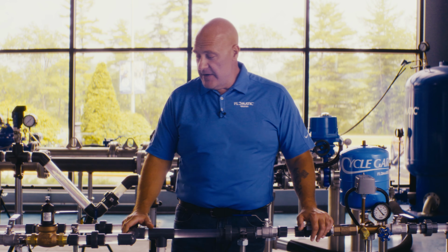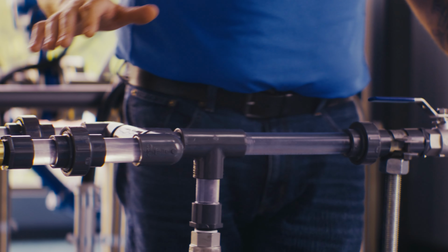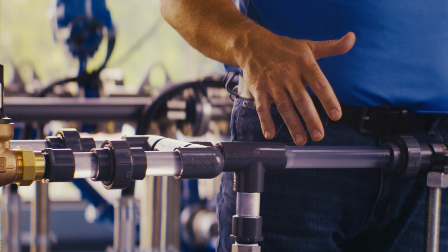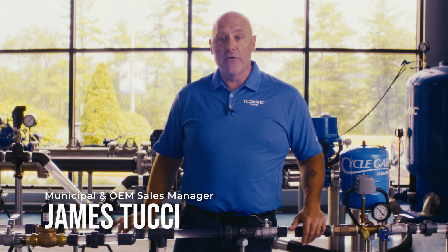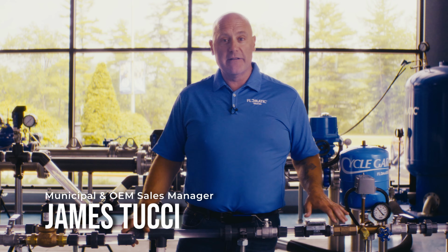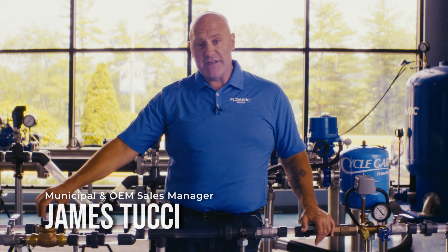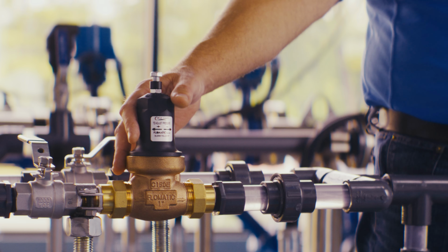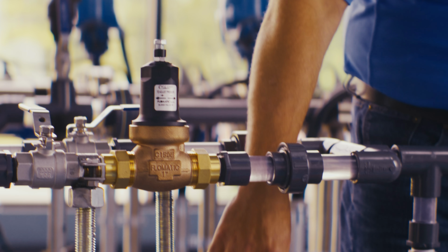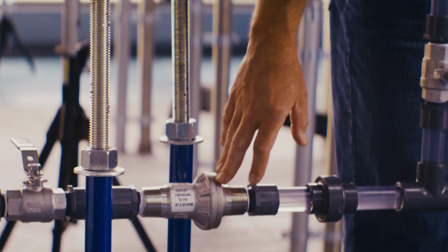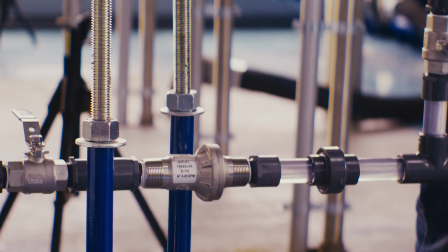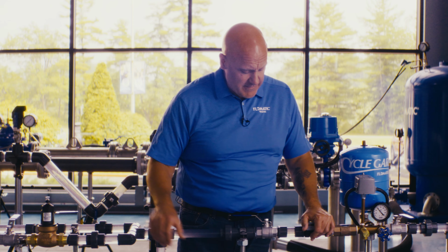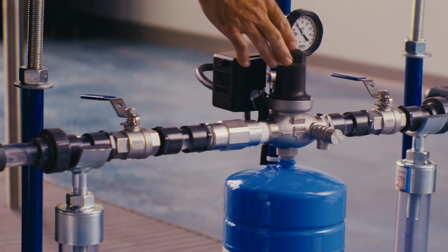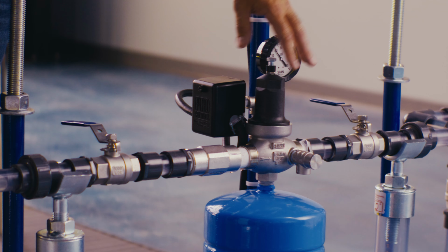So for our demonstration, what we have set up here is a couple different Cycle Gard units on a manifold system. We have a leg in this manifold that's going to show standard cycling of a pump without a Cycle Gard. We have our C152 unit, direct acting inline adjustable unit. Down below, we have our C153 stainless steel unit, which is intended to be used in the well with an in the well tank. And last but not least, we have our Cycle Gard 4 CB152 SST, another inline direct acting adjustable unit that is used as a tank T package.